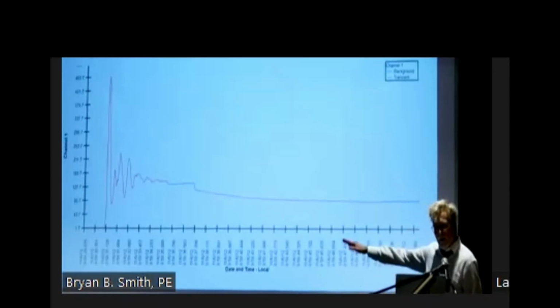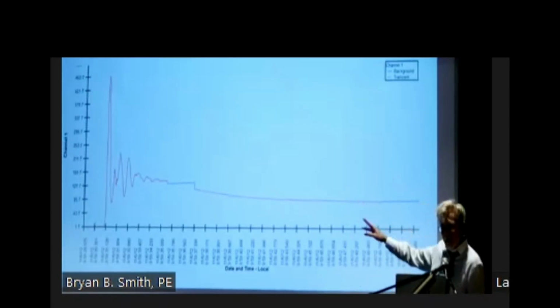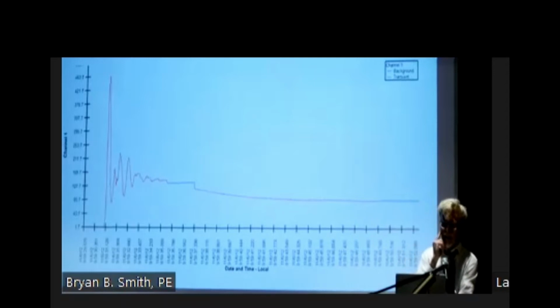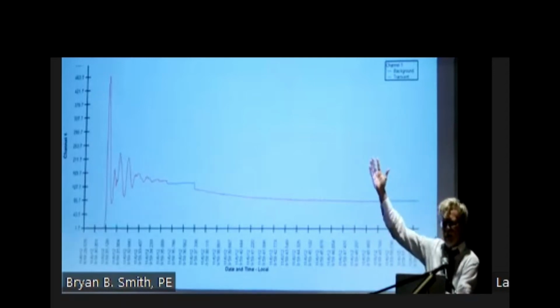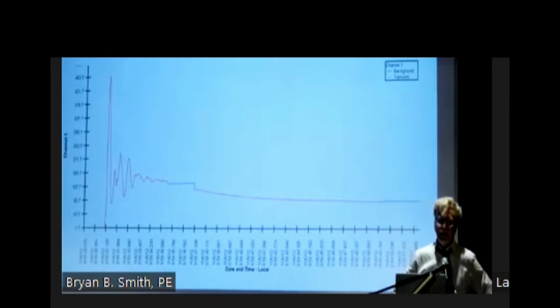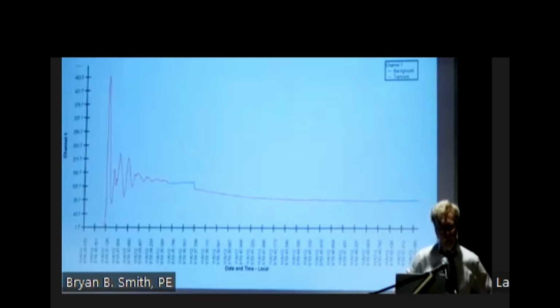And you can see when we're in steady state, it's like, oh, it's all good. The only problem that happened here was my piping didn't make it through the 463 PSI. And of course, everyone in the room knows this is the contractor's fault. So the contractor fixes the pipe, starts it back up, and rips the flange off the pump.